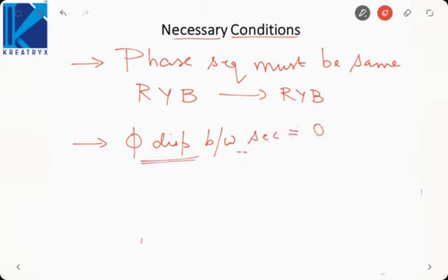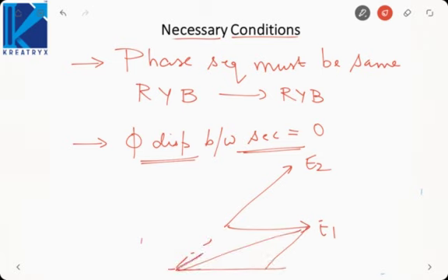Okay. The thing is, we are saying the voltage must be same. In phasor terms, same voltage or same phasor means the same magnitude and the same phase. Okay. Even if magnitudes are same and phases are different, the difference will not be 0. Suppose E1 is this and E2 is this. Both have same magnitude but different phase. Then E1 minus E2 will be something like this. It will be non-zero. Okay. We do not want that. We want that whenever we are subtracting the two voltages between the two transformers, the net voltage in the parallel operation should be 0 to avoid any circulating current. And for that to happen, the magnitude as well as phase of both the voltages must be same so that they can cancel out each other. If magnitude is same but phase is different, then also their difference will never be 0.